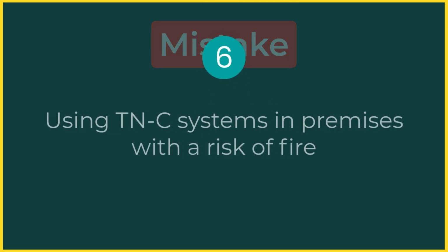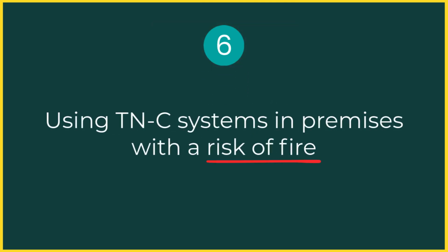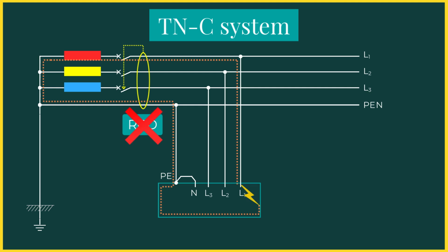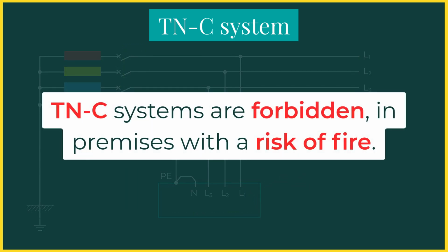Mistake 6. Using TNC systems in premises with a risk of fire. As explained in Mistake 5, RCDs cannot be used in TNC systems. This limitation has an important consequence. In many installations, RCDs are used not only for protection against electric shock, but also for fire protection. Since RCD-based fire protection is not possible in a TNC system, insulation faults may remain undetected for long periods. This increases the risk of fire. For this reason, TNC systems are forbidden in premises with a risk of fire.